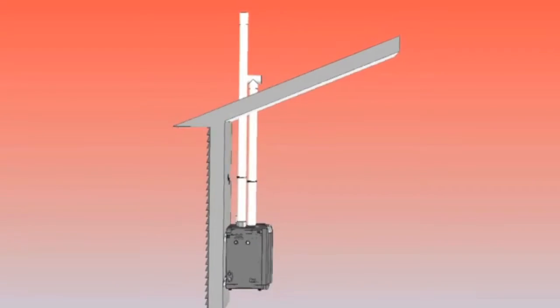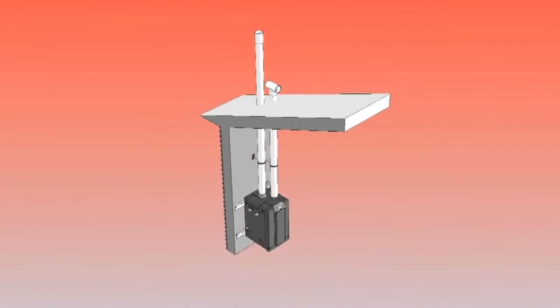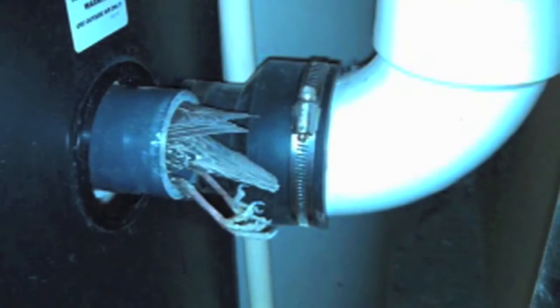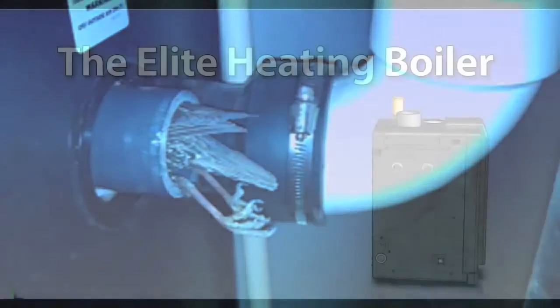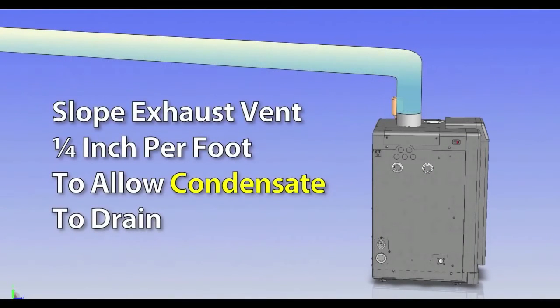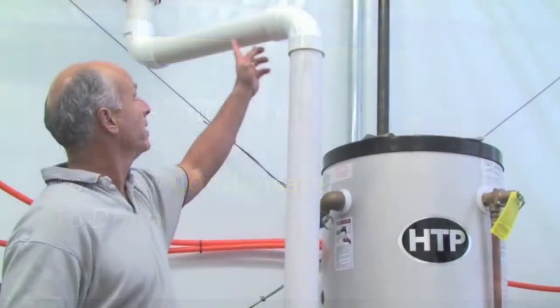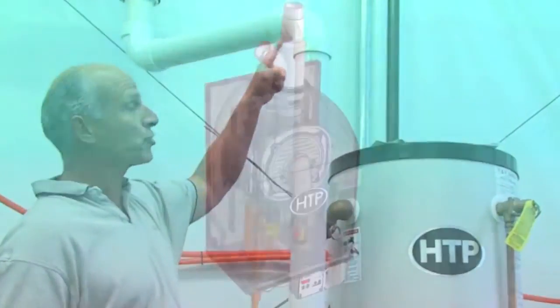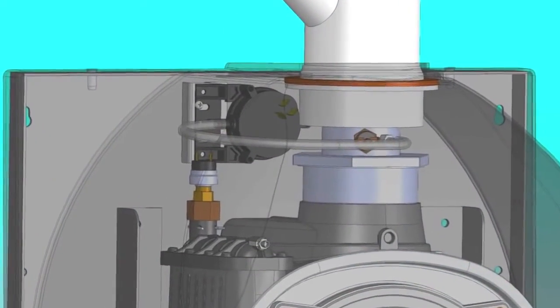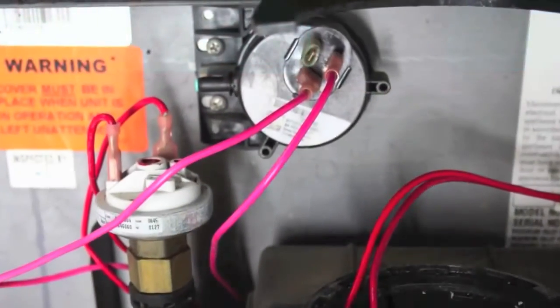To troubleshoot this problem, you will need to first examine the exhaust pipe and see if there is any blockage on the exhaust vent or outdoor terminations. Ensure all exhaust piping is pitched correctly back to the unit a quarter inch per foot, so there is no blockage or areas where puddling could occur inside the vent to cause excess pressure. If there is a problem, correct it and resume operation of the unit.